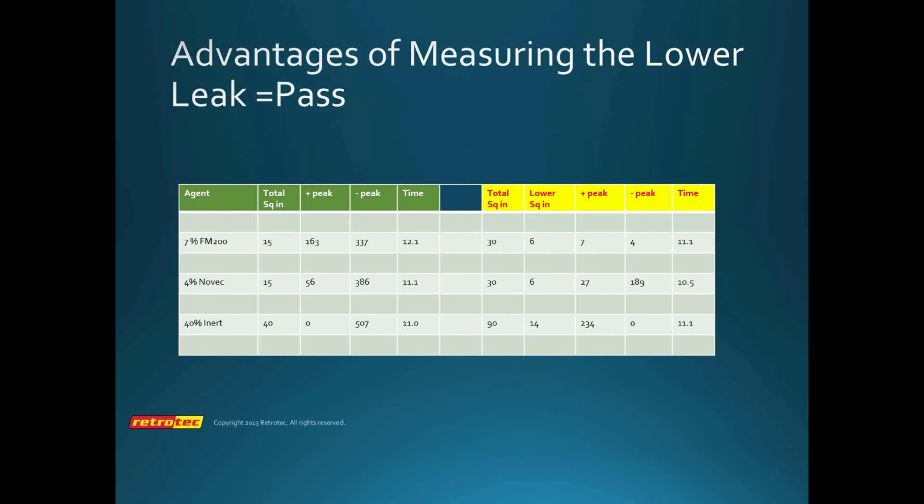But at the current time, we are now required to do a peak pressure analysis to see whether or not the enclosure is in danger when the system is discharged. So we want to find those enclosures that are at risk. Hopefully we can do this analysis before we do the installation and complete it. But at the very least, we should inspect it when it's completed to find out whether a risk exists.